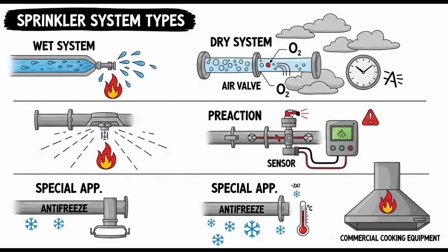Unlike wet systems where gridding can optimize flow, the complexities of managing air pressure, ensuring timely water delivery to all points, and achieving complete drainage in a gridded dry system are simply considered too problematic according to the standard. Too many potential points for trapped water or air issues. Okay, keep it simple with tree or loop layouts for dry pipe. Let's go back to quick opening devices, or QODs. You mentioned they help with water delivery time? Yes, QODs are listed devices, permitted specifically to accelerate the tripping of the dry pipe valve and help meet those water delivery time requirements. We talk about the 60-second rule, calculations, manifold test, or other listed criteria.